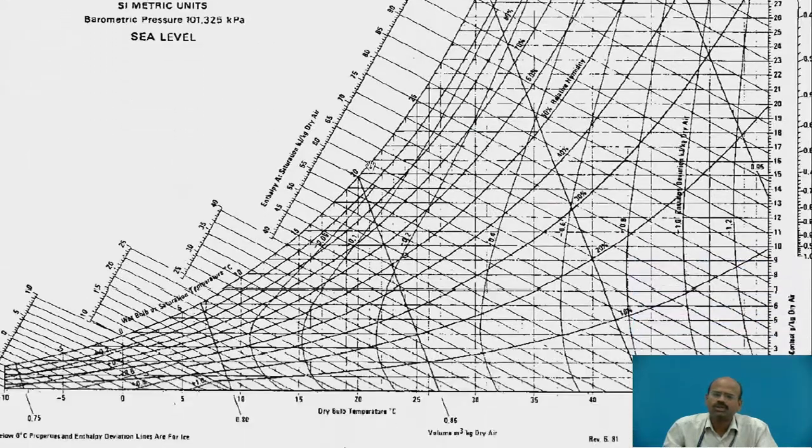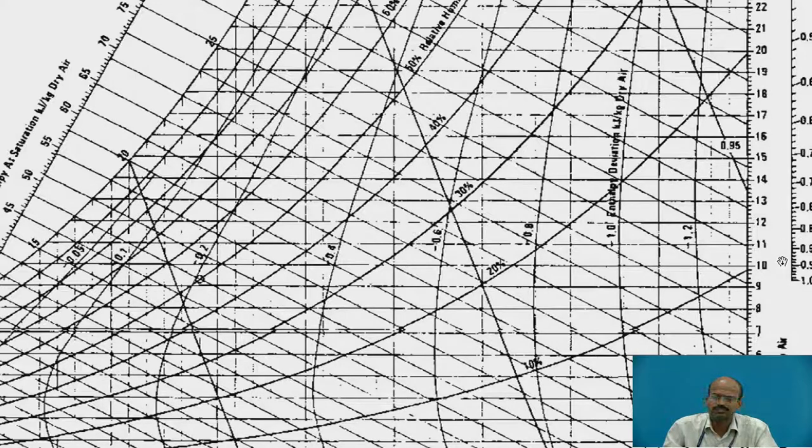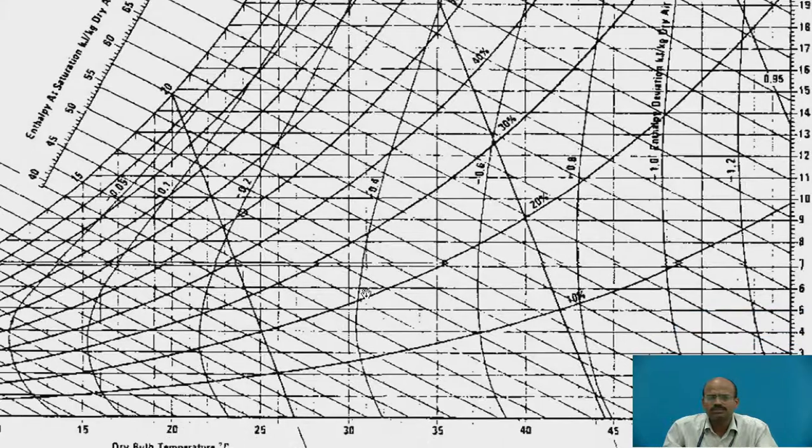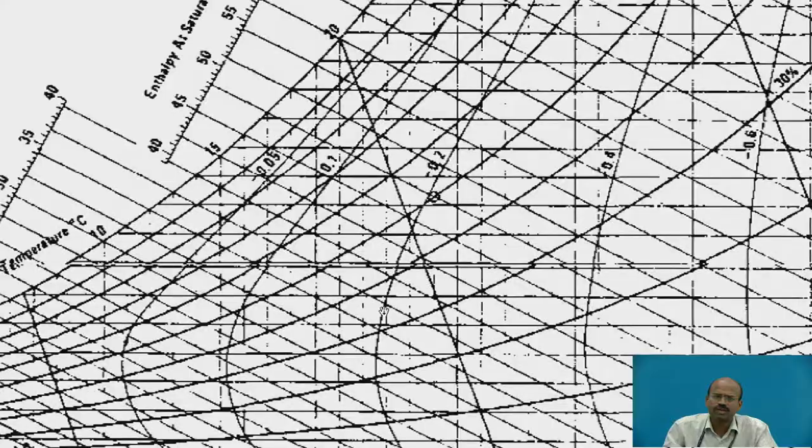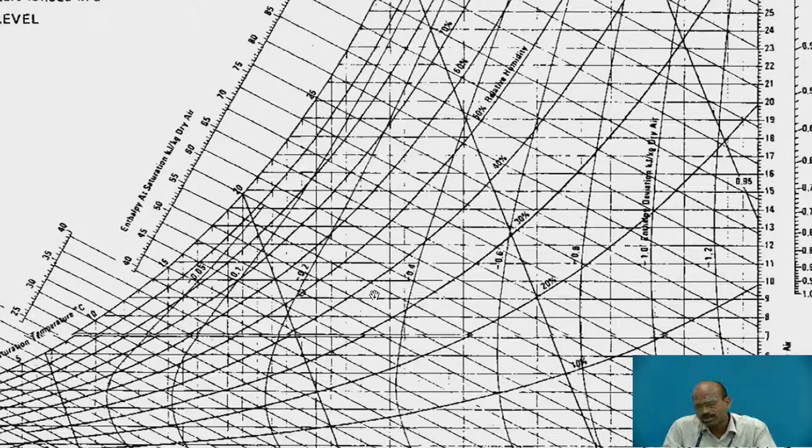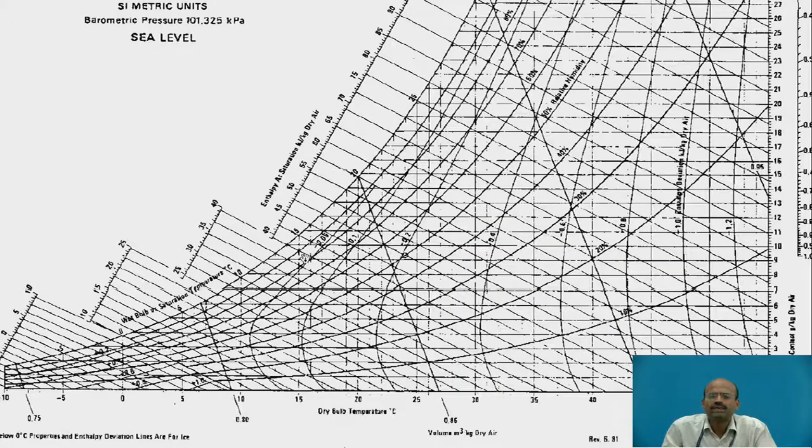Then, on this psychrometric chart, on right hand side, there is SHF scale. This is the sensible heat factor scale. It will start from 1 to 0.75. To draw this scale, there must be some reference point. On the carrier psychrometry chart, this circle is the reference circle. We have to align the set square to this reference circle and the obtained SHF value. Then, we can draw the sensible heat factor of that particular room load, because room load will have sensible heat and latent heat. Any inclined line will have some value of SHF as it consists of sensible heat and latent heat.